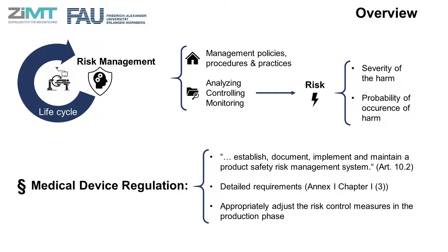The Medical Device Regulation (MDR) outlines in Article 10.2 that manufacturers are required to establish, document, implement, and maintain a product safety risk management system. The detailed requirements of what the risk management system will cover are listed in Annex 1, Chapter 1(3) of the MDR. In addition to this, the MDR outlines that in the production phase, manufacturers must evaluate the impact of any new information and, if needed, adjust the risk control measures appropriately.